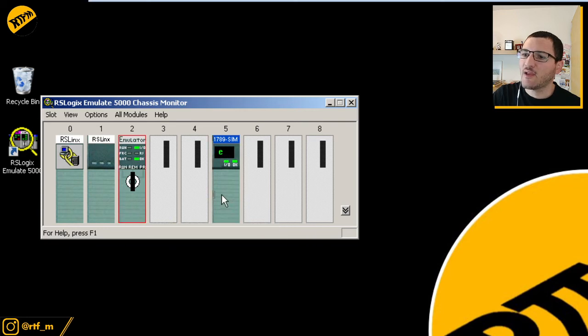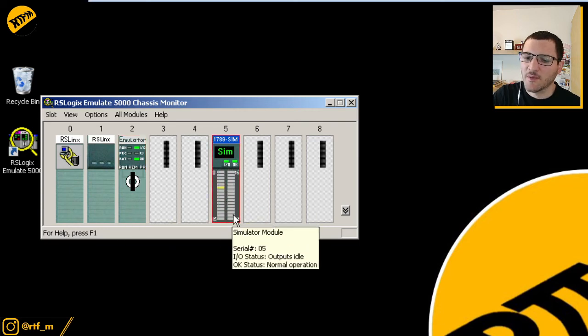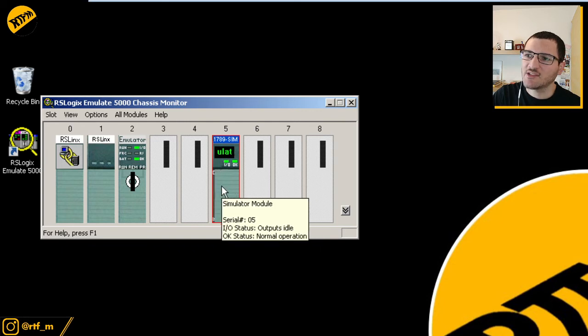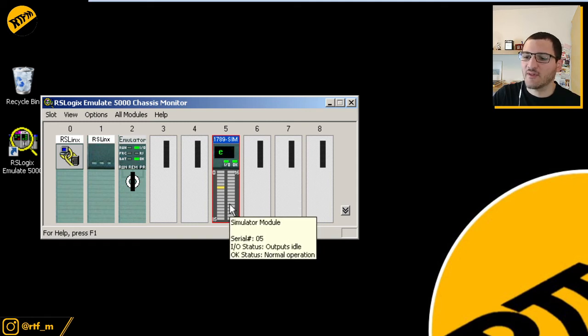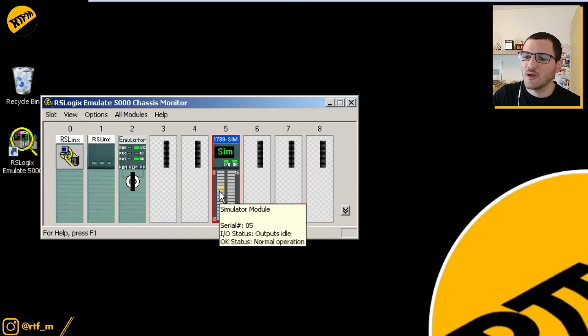If you press it on the I/O module, it opens up and shows you the states of those LEDs, displaying whether an input is actually live or in a true state. You can see that one of the I/Os here is set to 1, which means there is a controller loaded and it is driving either an input or an output on this module. Okay, so you can also push to close that. Pretty handy, isn't it? It's very nice.